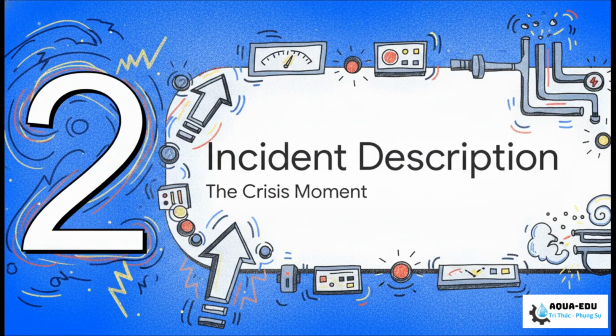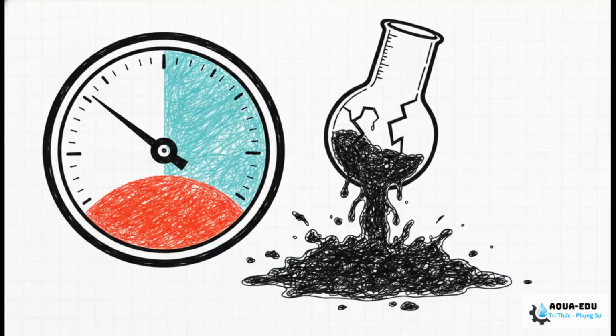Moving to Section 2, Incident Description and Symptoms, the crisis moment. Okay, picture this. You've just finished a complete regeneration cycle on your mixed bed. You're feeling good, you put the unit back online, but instead of seeing that pristine water, the quality just crashes. Your resistivity plummets below 10 megaohms, and the lab is suddenly reporting severe silica leakage.